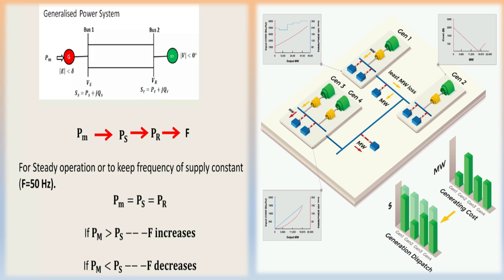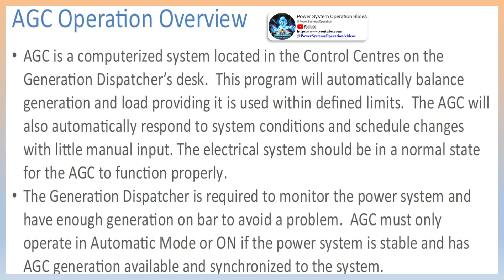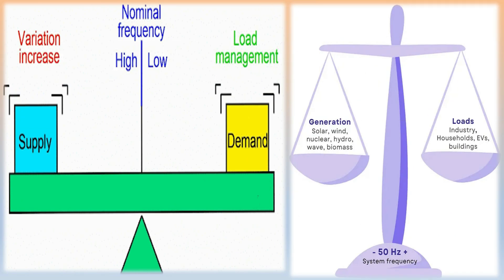Basepoint: it is the desired unit baseload. Setpoint: it is the desired generation output of a unit. Regulating mode: it indicates that the AGC regulator is active. Before entering regulating mode, the generation dispatcher must check that there are no tripping conditions prevailing and that the regulating margins and spinning reserve are sufficient.